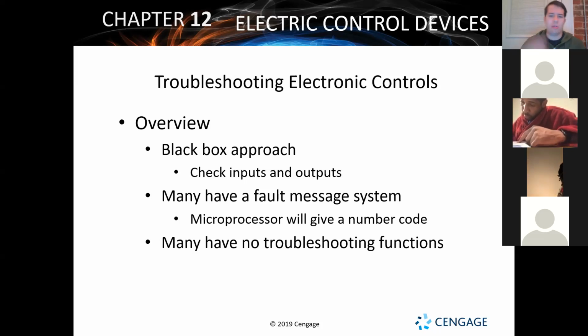Other thing, don't forget, always look at those fault messages. If it's got an LED code, some of them will have an LCD code where it looks more like an old school digital alarm clock, and it'll just send a number like 34 or 7B or 8C or something like that. And again, you just go to the diagnostic sheet, and it'll tell you what that code means, whether it's a motor not working or a switch not operating or something going into a fault, or it could just say system not operating, and it's not going to give you any help, because some of them do that.